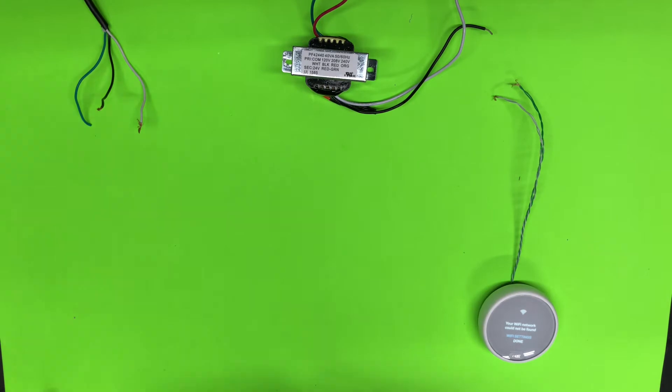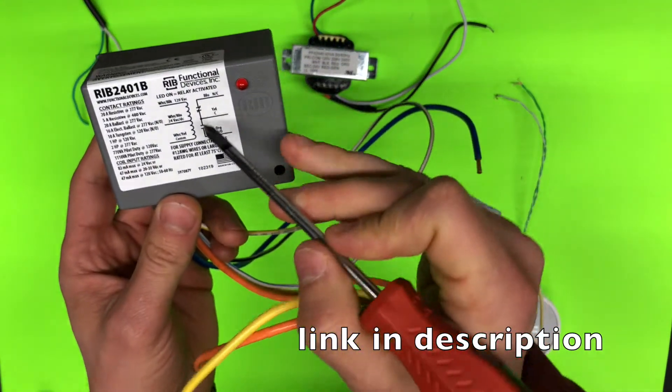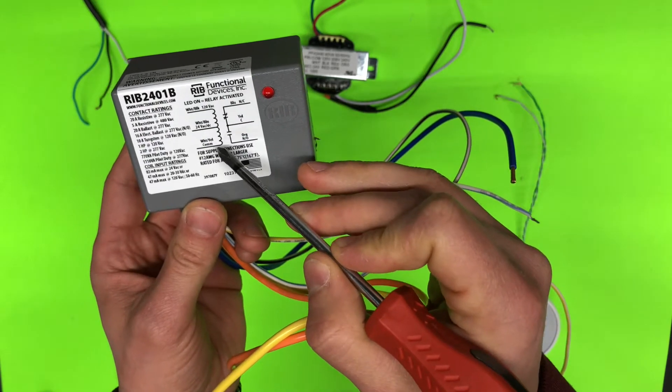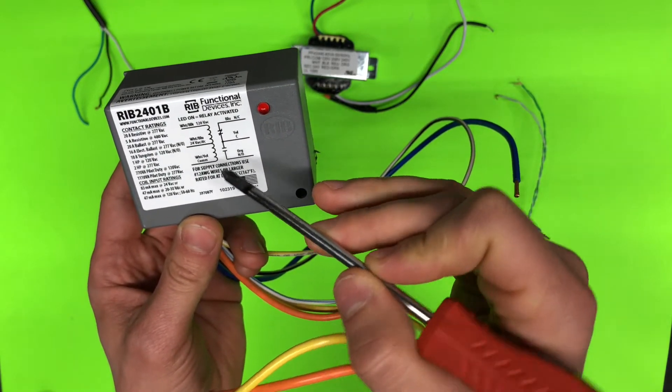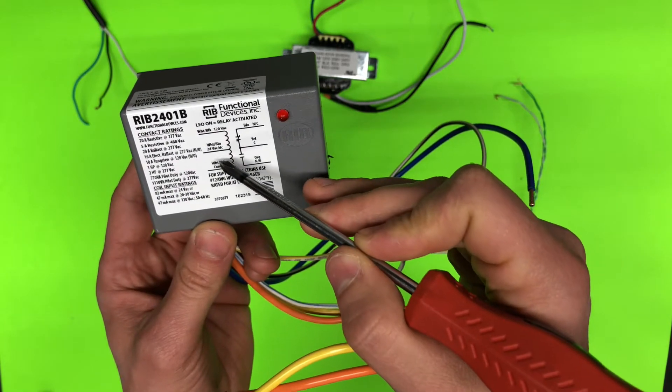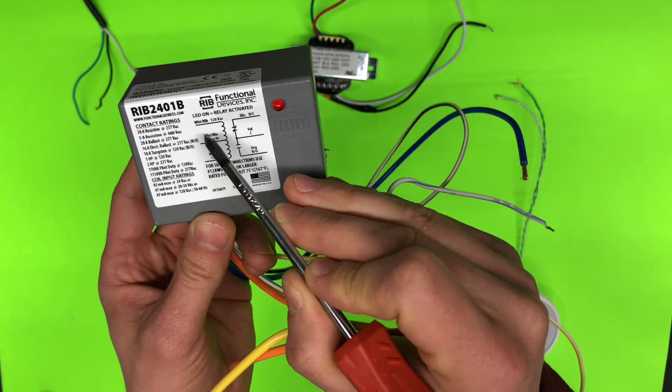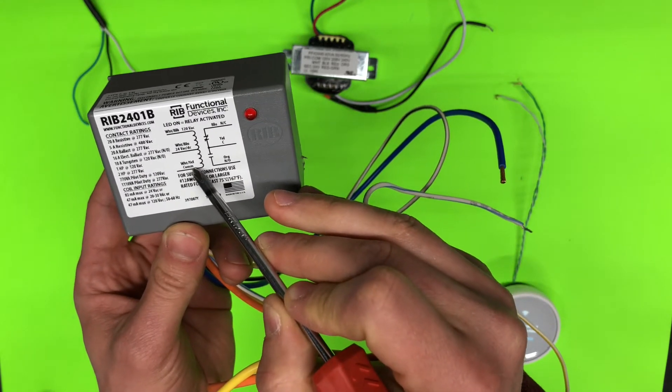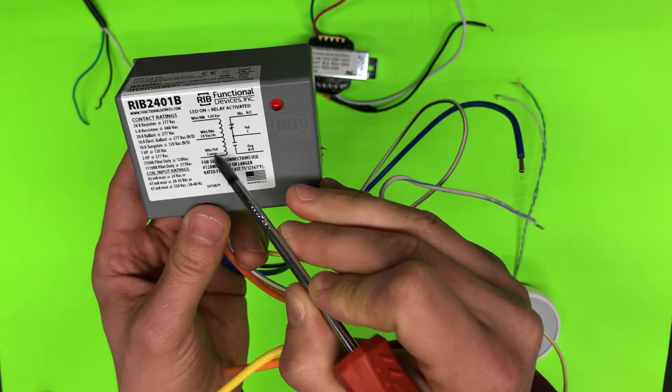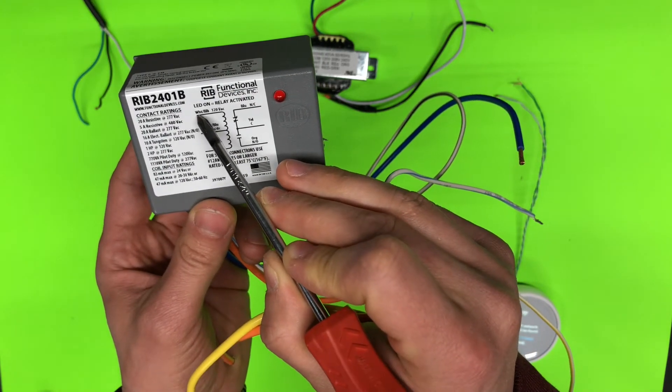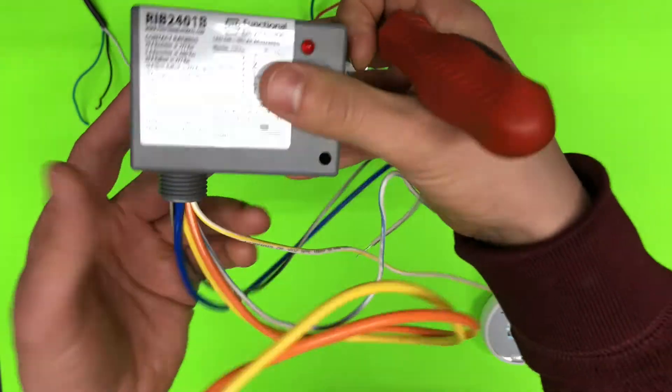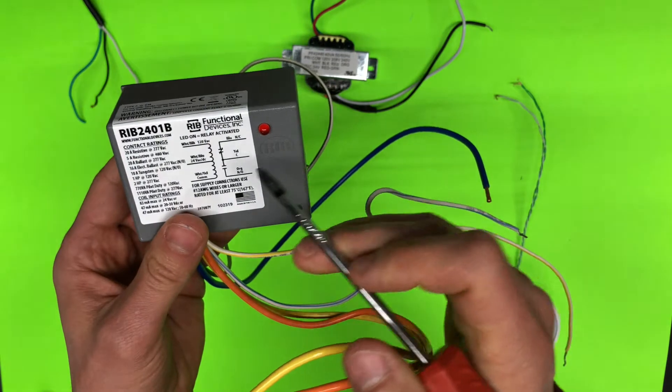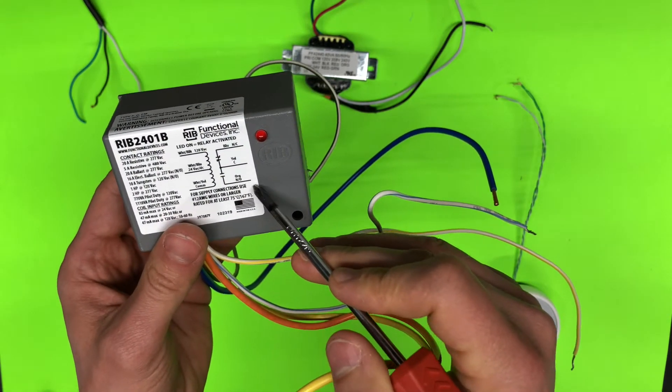Then we will use a relay. So the relay has, on the left side here, it has low voltage as well as high voltage input. That means we can close this relay with 24 volts AC or DC or 120 volts. I'm going to use 24 volts because our thermostat will send this signal, it's low voltage, so I don't need the white black cable.